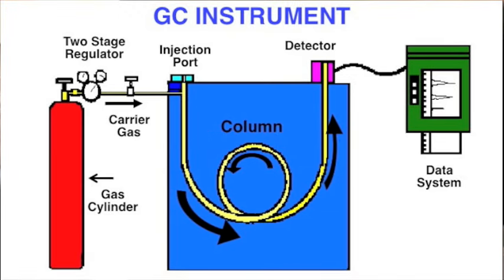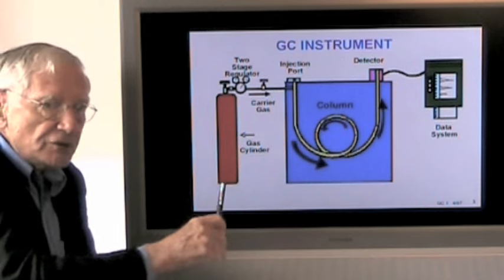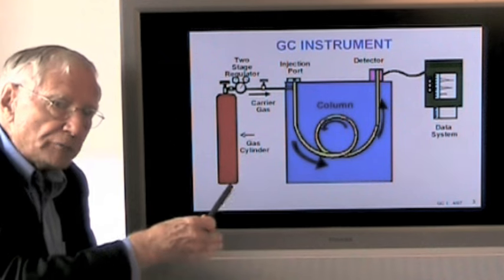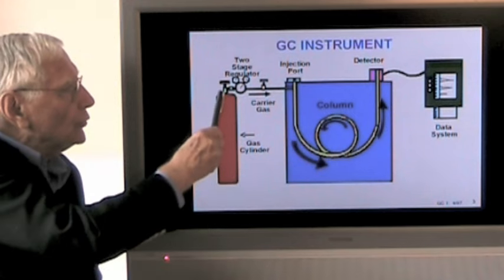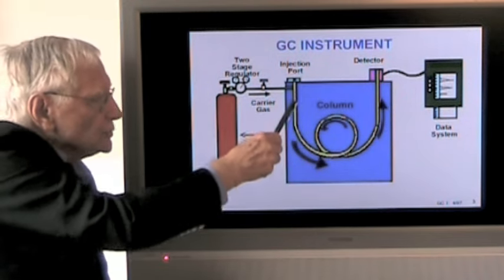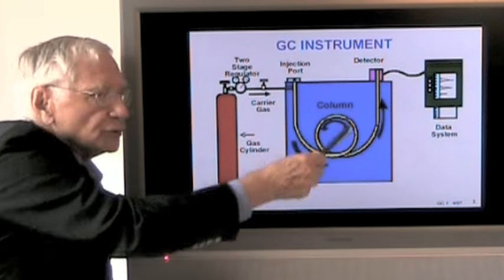The GC instrument responsible for the separation consists of several components. A gas cylinder here, let's say of helium, a two-stage regulator, where the first stage shows you the gas pressure left inside the cylinder. The second stage is set by you, the operator, to sometimes 40 or 60 PSI. This pressure then drives the carrier gas through an injection port, a column, and on to the detector.